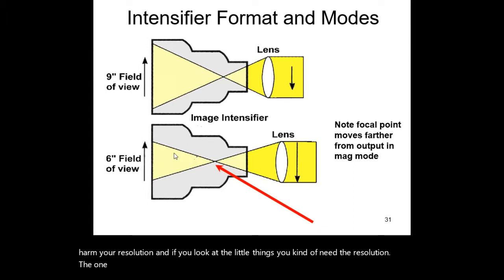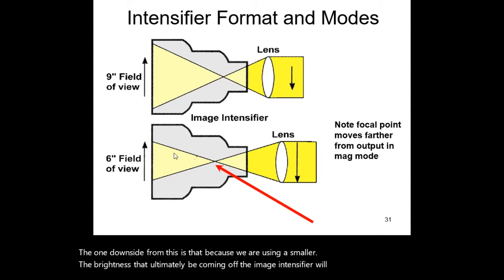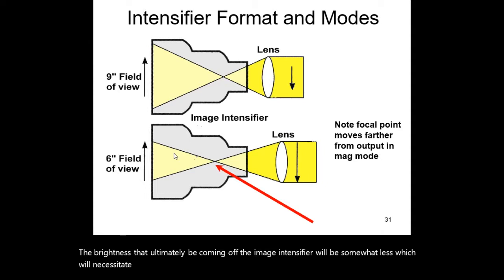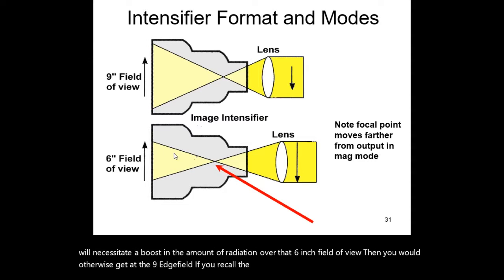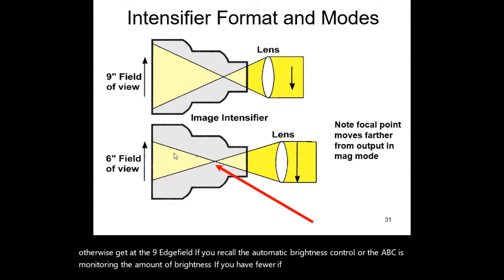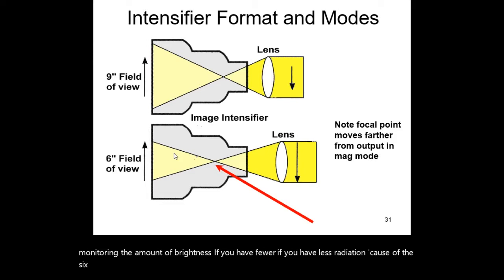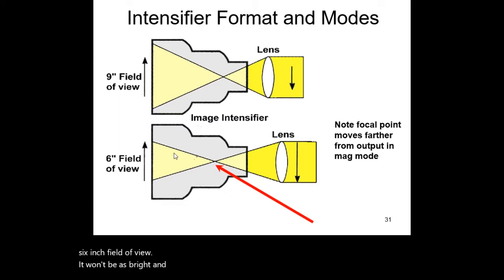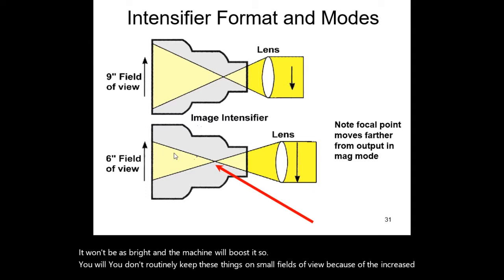The one downside from this is that because we're using a smaller field, the brightness that ultimately will be coming off the image intensifier will be somewhat less, which will necessitate a boost in the amount of radiation over that 6-inch field of view than you would otherwise get at the 9-inch field of view. Recall, the automatic brightness control, the ABC, is monitoring the amount of brightness. If you have less radiation because of the 6-inch field of view, it won't be as bright and the machine will boost it. So you don't routinely keep these things on small fields of view because of the increased radiation dose.